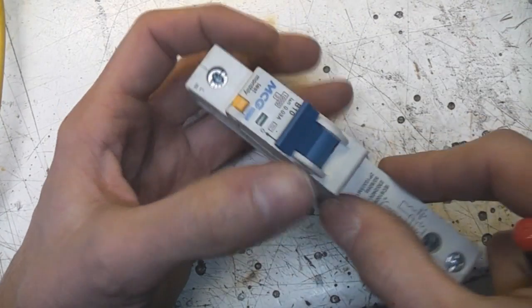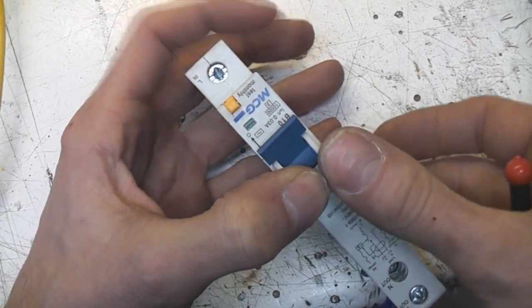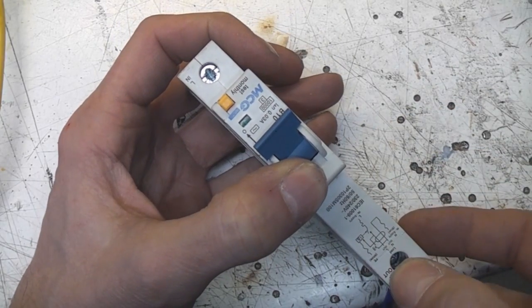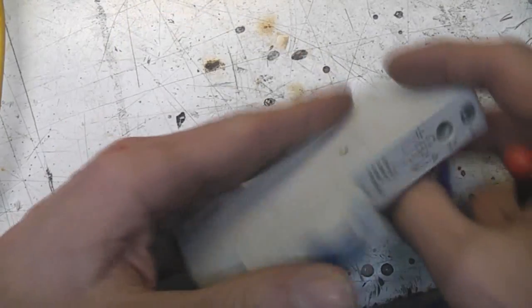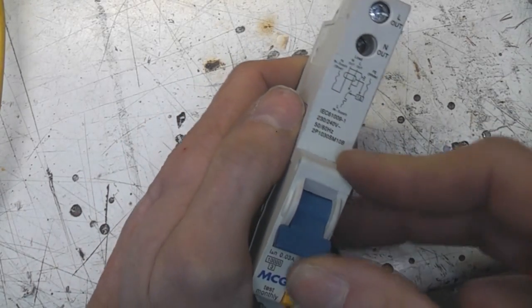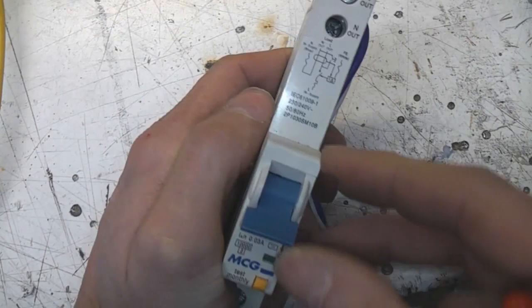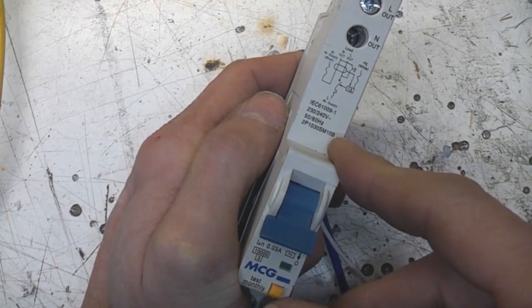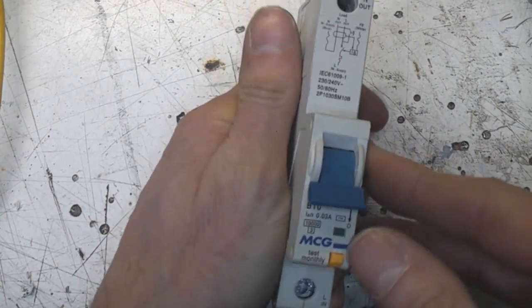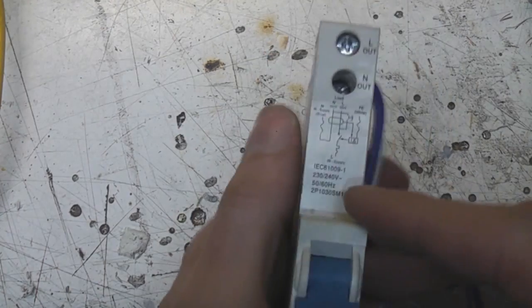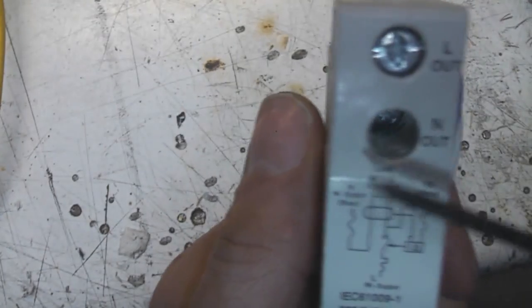So it's basically a combination of a traditional overcurrent circuit breaker and a residual current device. Different countries have different names for these. Sometimes in the US I think they're called GFCIs, ground fault circuit interrupters, or earth leakage circuit breakers. They're fairly common, but the names can change depending on where you are. And it's got a handy little diagram on here to show you what it does.